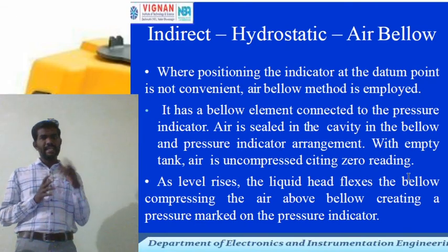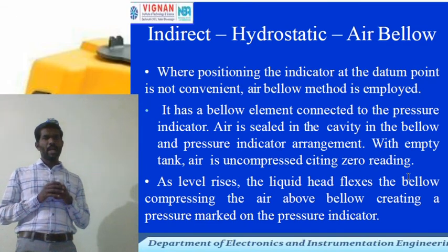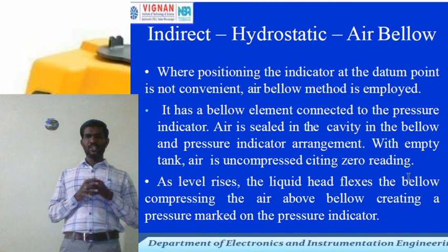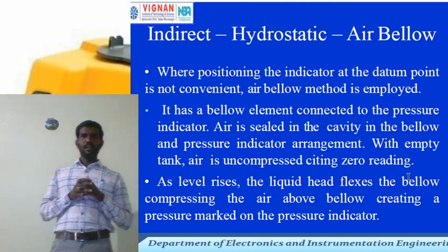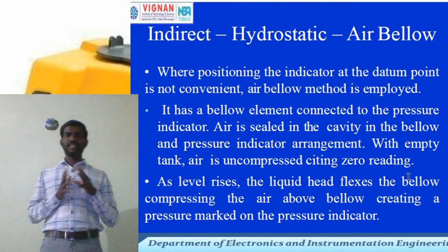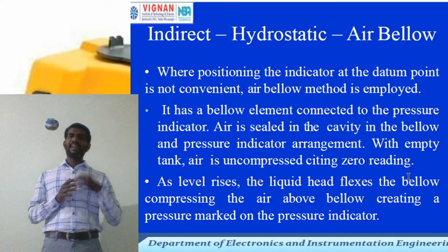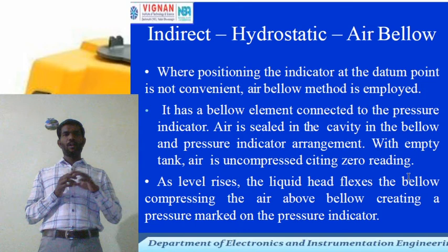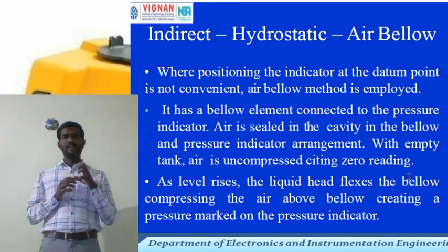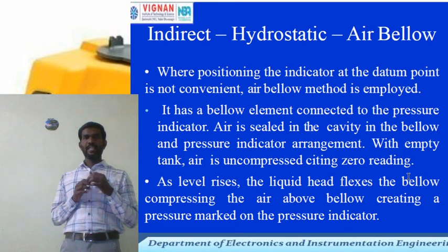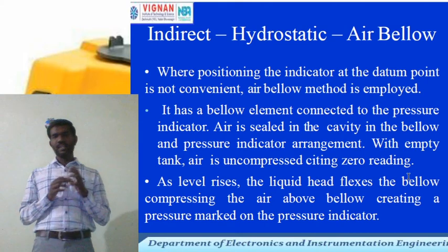Air is sealed in the cavity in the bellow, and a pressure indicator is arranged there. Okay, with an empty tank, the air is uncompressed, which indicates zero. As the level rises, the liquid head flexes the bellow, which compresses the air above it, creating a pressure marked on the pressure indicator.